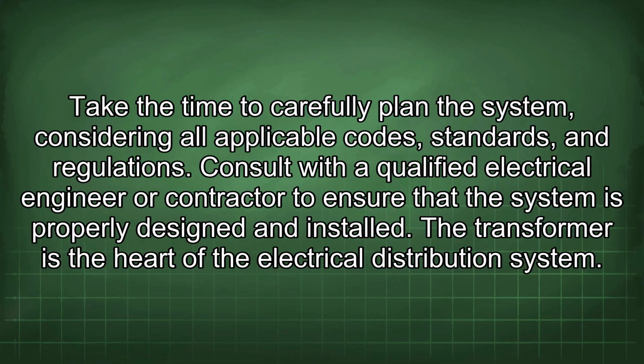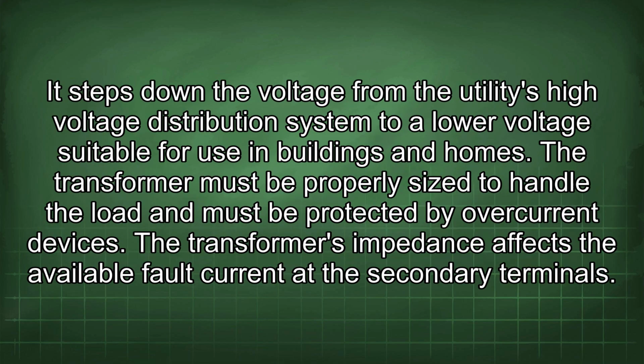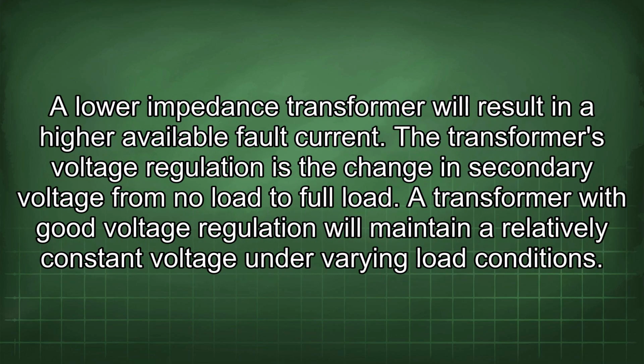The transformer is the heart of the electrical distribution system. It steps down the voltage from the utility's high-voltage distribution system to a lower voltage suitable for use in buildings and homes. The transformer must be properly sized to handle the load and must be protected by overcurrent devices. The transformer's impedance affects the available fault current at the secondary terminals. A lower impedance transformer will result in a higher available fault current. A transformer's voltage regulation is the change in secondary voltage from no load to full load.